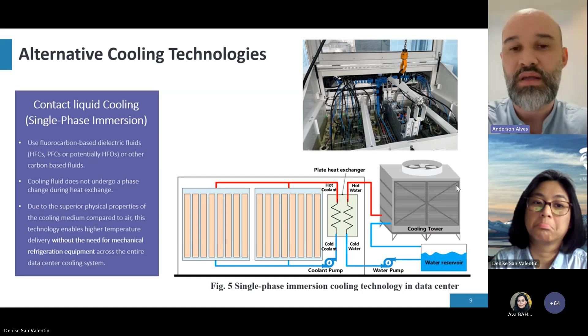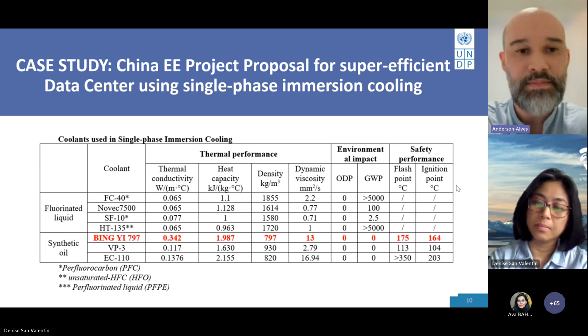Next slide, please. So the proposal of the China project, on top of using this single phase immersion technology, was also to use a synthetic oil that has zero GWP, in comparison to other fluorinated liquids with high GWP that are also used in this technology, as an additional environmental benefit to the project. So basically, we would go completely away from HFCs and completely meet the requirements of the Kigali Amendment, that is, to reduce the demand for these refrigerants. Next slide.